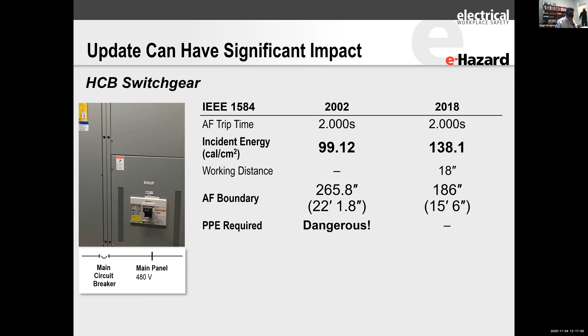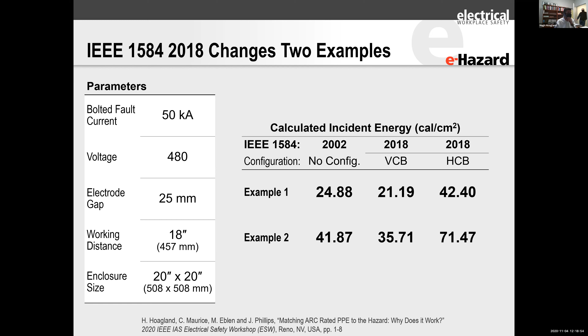Here on example number 1, using the 2002 model we came up with 24 calories per centimeter squared. With 2018, we enter it and come up with something in the ballpark of 24 calories per centimeter squared. However, if we correct the copper bus configuration, we can see that the real energy is 42 calories per centimeter squared. In another example, where we had 41 calories from actual testing using the 2018 model, we now see that the real value is 71 calories per centimeter squared. Actually, I used the wrong vocabulary there. Using the 2002 calculations on the previous example, we ended up with 40 calories per centimeter squared. Now, fixing it, we get 71 calories per centimeter squared, which is much closer to the actual value that you measure using a calorimeter.